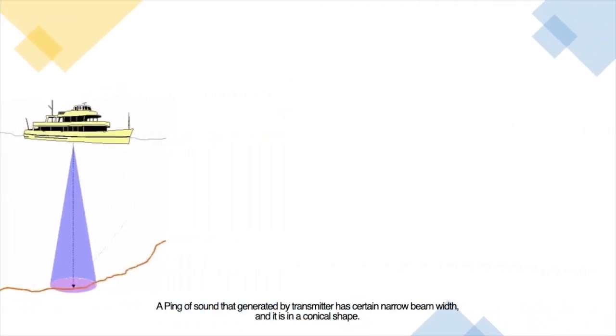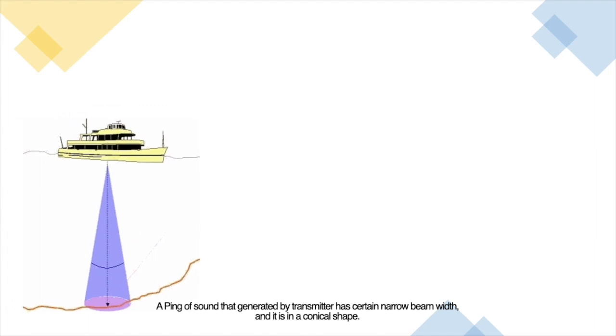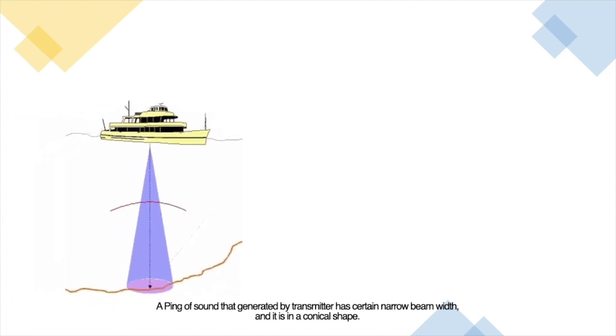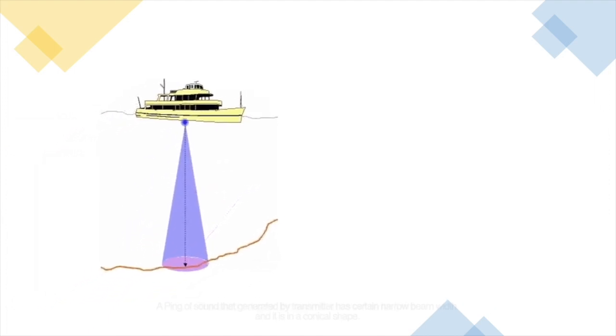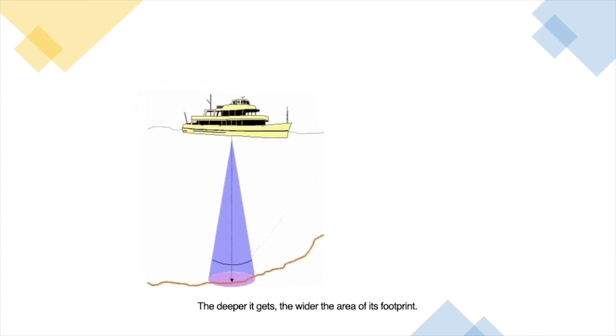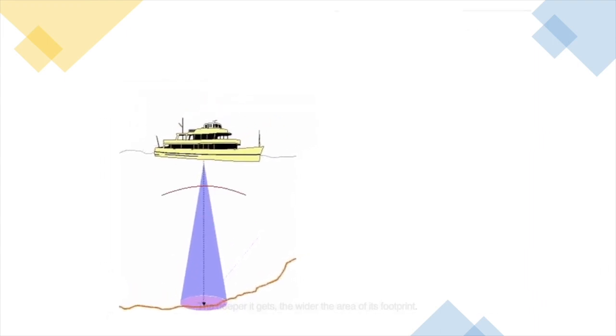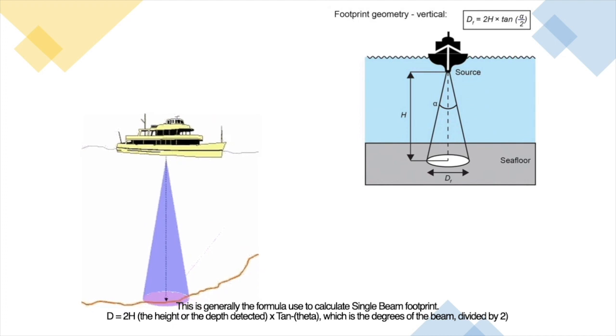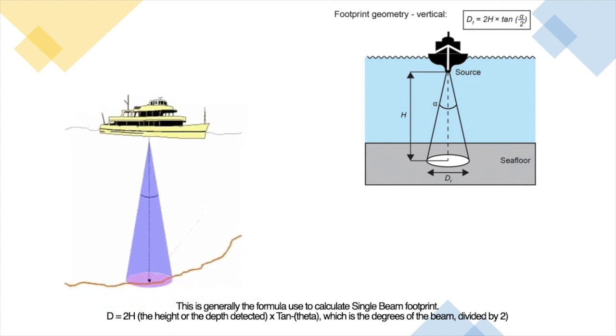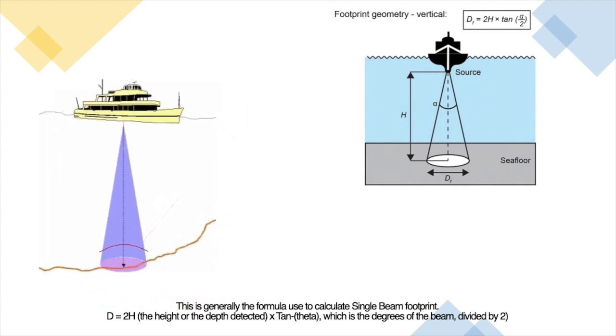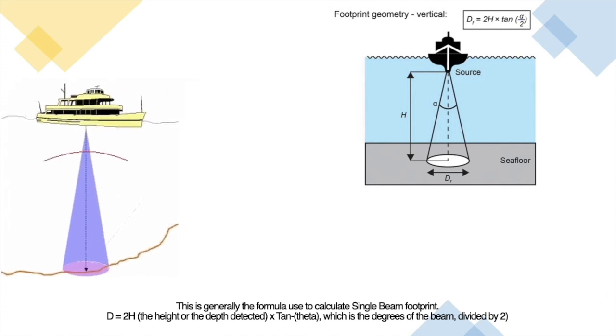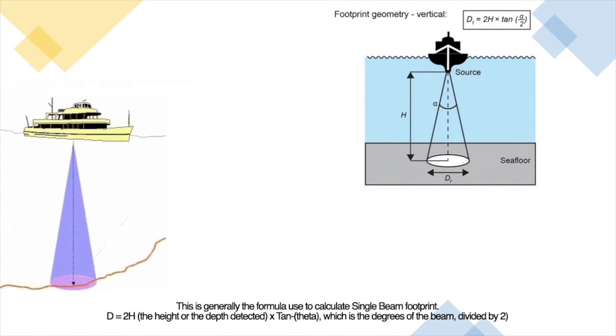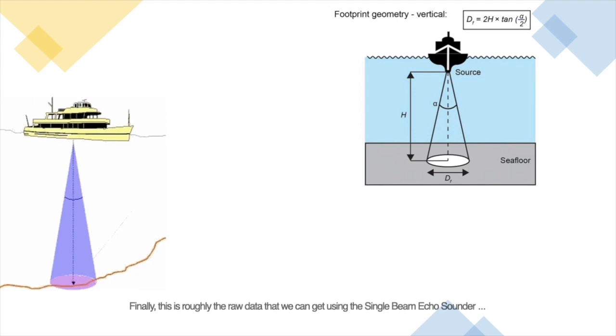A ping of sound generated by the transmitter has a certain narrow beam width, and it is in a conical shape. The deeper it gets, the wider the area of its footprint. This is generally the formula used to calculate single beam footprint: D equals 2h times tan theta, where h is the depth detected and theta is the degree of the beam, divided by 2.